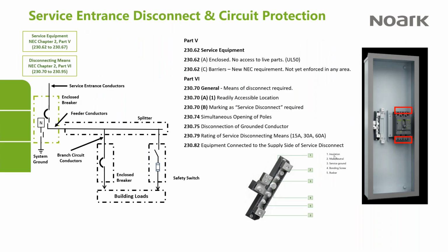Okay, so in Article 230, Part 5 defines service equipment, and there's two parts of it. The first part is really general, Clause 230.62, and it basically says it has to be enclosed with no access to live parts, and that brings you to the enclosure rating under UL 50. There's a new requirement in the NEC, which requires barriers for the line side, that's the utility side of the disconnect device. And you see on the picture to the right here, I've just highlighted where this barrier system would go. This is new in the NEC.